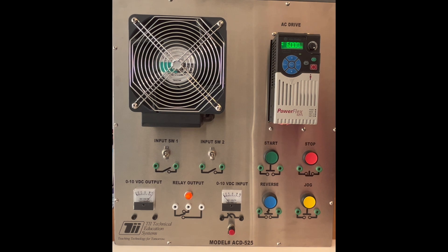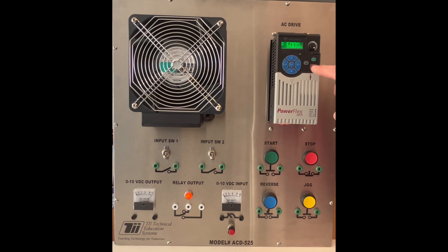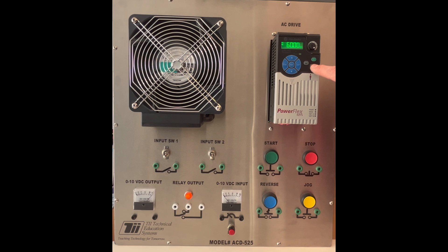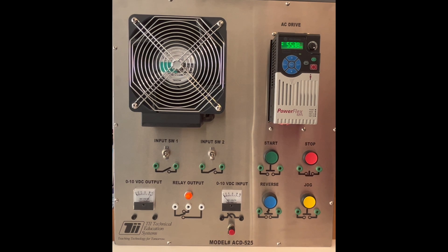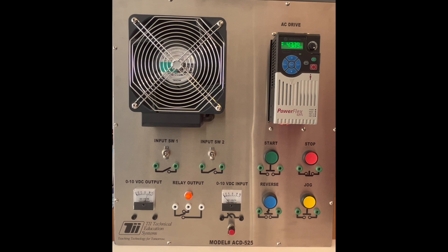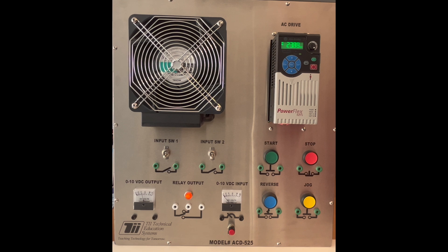Now I'm going to hit the stop button and we'll see how slow and how long it takes to actually decelerate the AC motor. So we went from 10 to our setting of 15 seconds and you can see it's taking much longer to decelerate the motor than it would as if we had left it at the factory settings of 10.